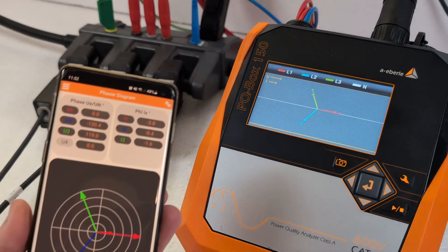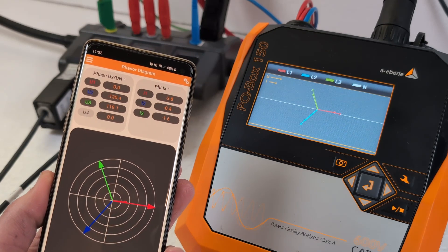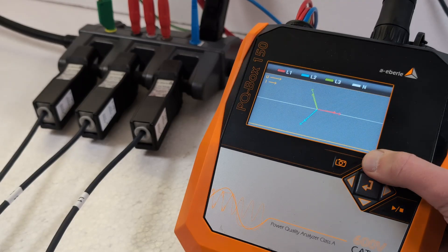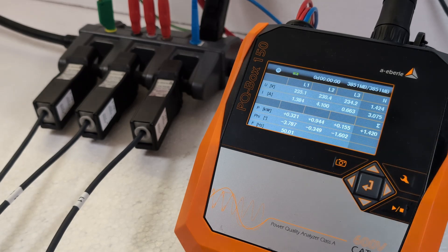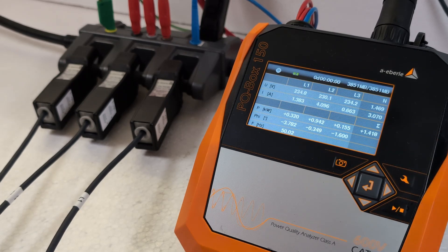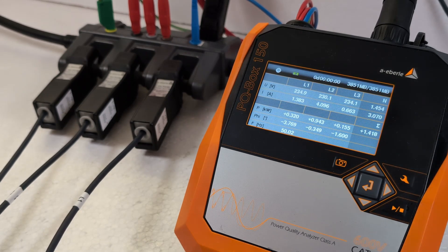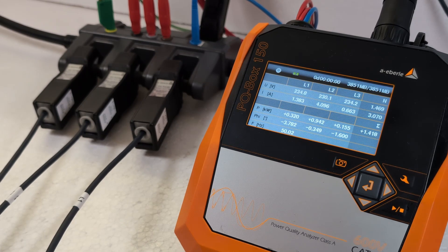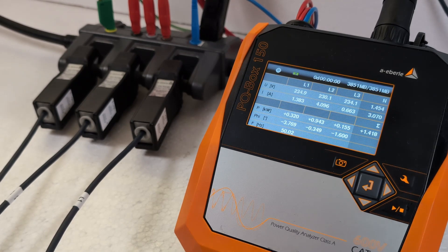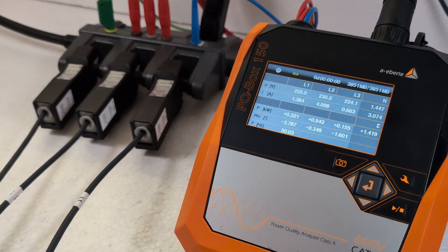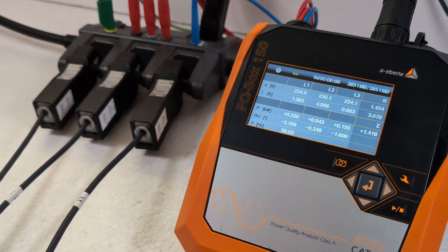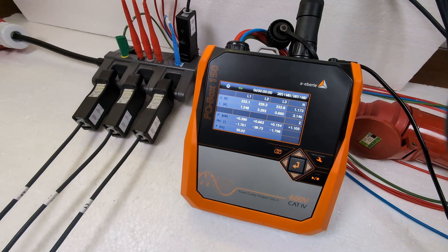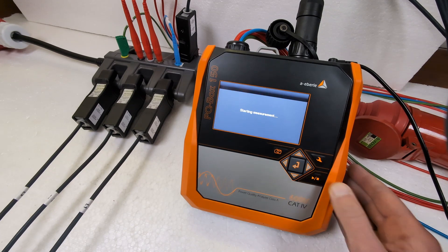I can also see all of this in the PQBox app. I press the up button and return to the table view. All three active powers are now positive and the phase angles phi between current and voltage are also within an acceptable range. So I have checked the connection of my PQBox and can now start recording. To do this I briefly press the start stop button once.